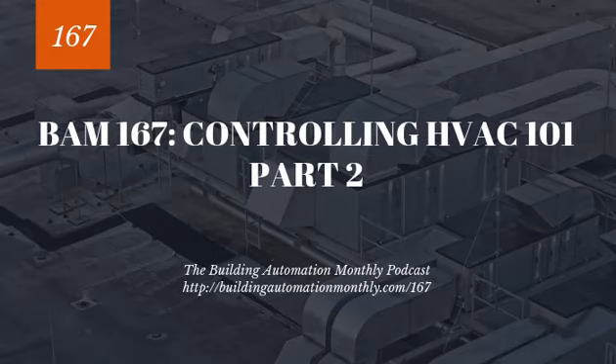This was especially true on 100% outdoor air units where there is no return duct. Normally the return and the outdoor air damper are opposing one another. They're installed as such, so as long as they don't slip on the damper shaft, they're going to oppose each other. So if you have 100% outdoor air, you will have 0% return, and if you have 100% return, you'll have 0% outdoor air. As long as that linkage or the programming is proper and the actuators aren't slipping on the shaft, you should not have issues with your damper states.